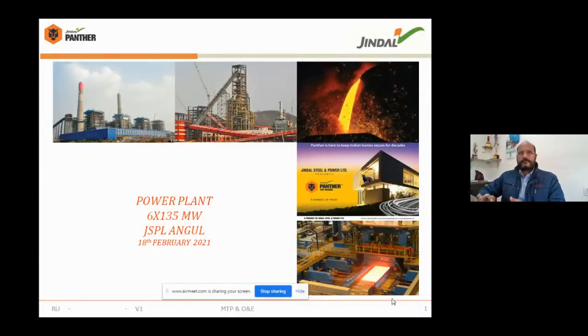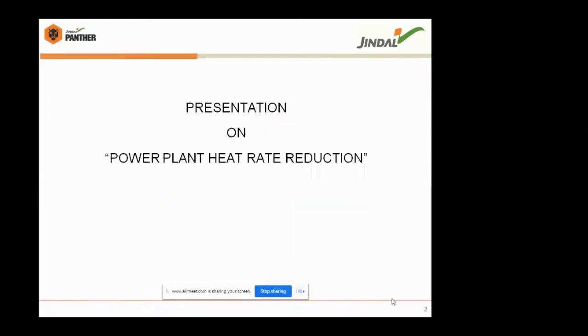Yes. Steel plant of 4.5 million ton capacity, and we are supplying power to our customer, that is a steel plant. We have 6 numbers of units, each having a capacity of 135 megawatt. Each unit has one boiler and one turbine TG set. The boiler is of CFBC kind, circulating fluidized bed combustion.